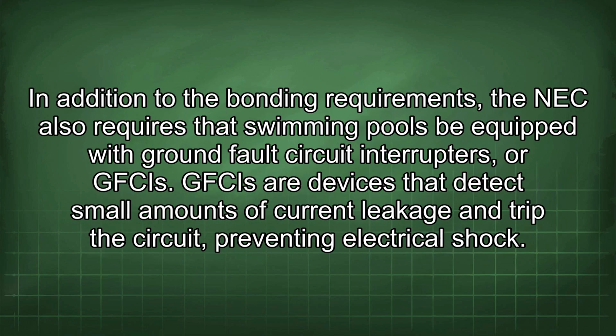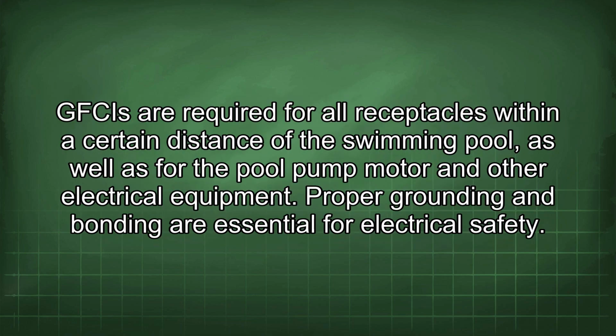In addition to the bonding requirements, the NEC also requires that swimming pools be equipped with ground fault circuit interrupters, or GFCIs. GFCIs are devices that detect small amounts of current leakage and trip the circuit, preventing electrical shock. GFCIs are required for all receptacles within a certain distance of the swimming pool, as well as for the pool pump motor and other electrical equipment.